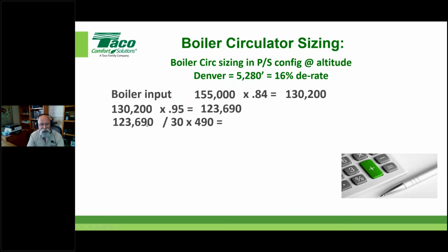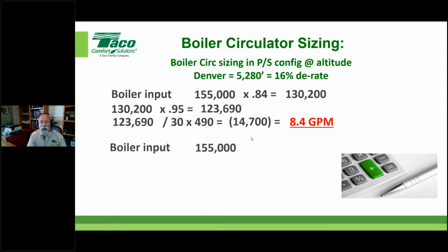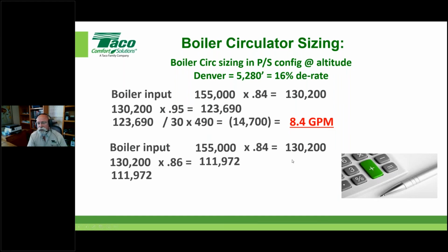Here's that same math that I just showed you at altitude, okay? So you're at 8.4 gallons a minute. John, this goes right to what you were emphasizing before. What if I wasn't doing something as efficient, and I look here, 0.86. That gets me down around 7 gallons a minute. Exactly what we had talked about on that last emphasis that you made. Okay. So anyway, folks, just understand these boiler circulators should be and can be smaller than you have imagined in the past.